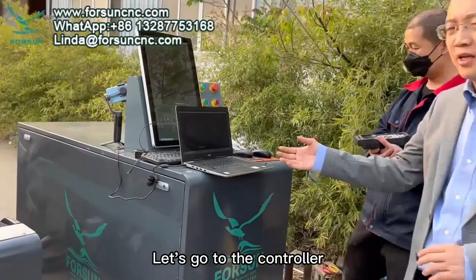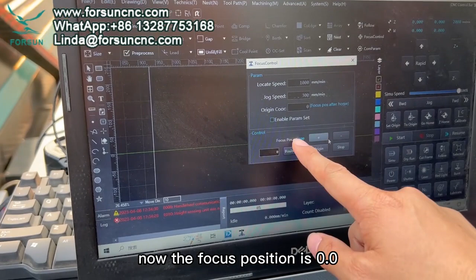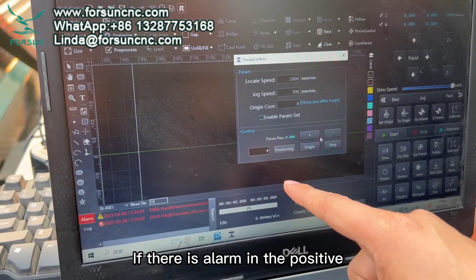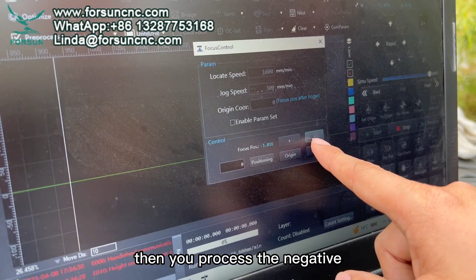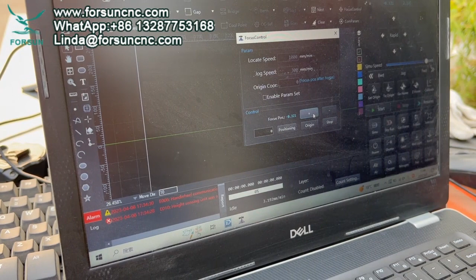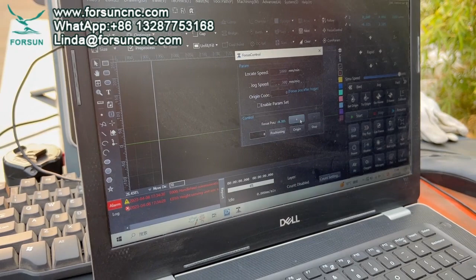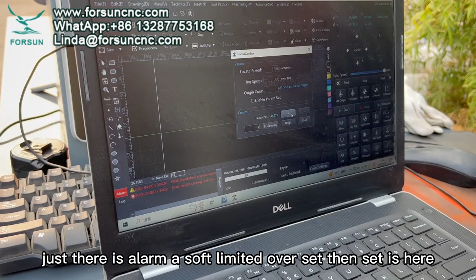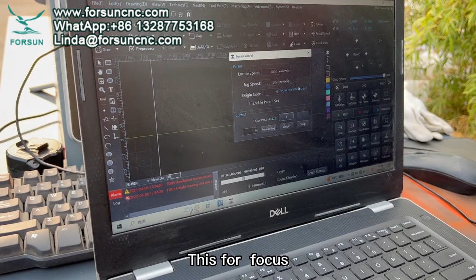If that happens, we must find the focus control. Let's go to the controller. We find the focus control, press it, okay, you can see here. Now the focus position is 0.0. If there is an alarm in the positive, then you press the negative. If it shows negative, then you press the positive, to find the focus position. This setting is not always changed — just when there is an alarm or soft limit exceeded, then you set it here. This is for focus, okay.